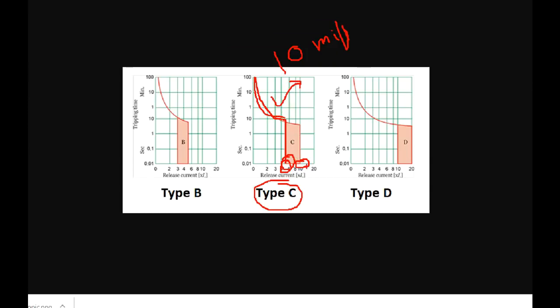Type C curve will operate at 6 to 10 times the rated current. Type B will operate at 3 to 5 times. Type D curve will operate at 10 to 20 times. Now we will mention what type of C curve is used and the tripping time is also mentioned.